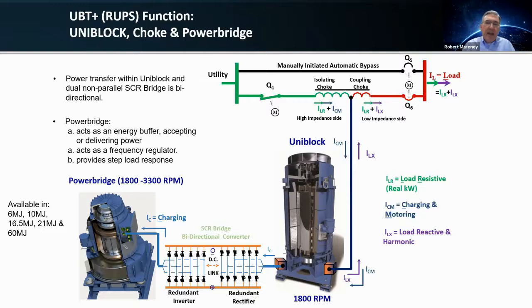So I can absorb that excess generated power into the flywheel. Obviously, it speeds up a little bit, and I can hold that energy there until the microgrid bus stabilizes. And then as it stabilizes, I can slowly feed that stored energy in the flywheel back onto the microgrid bus, bringing the flywheel energy storage device back to nominal speed. So a nice benefit of having that ability to run the flywheel at multiple speeds is being able to take power in or out based on application of the output side of the UPS, which is not available to you in other applications. So it provides a lot of flexibility in a lot of applications. We've been doing these for a long time. So let's move on.